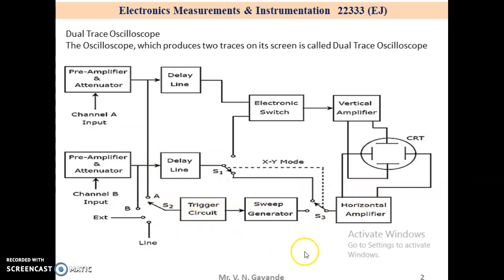The horizontal deflection system is common for both input signals or channels. The horizontal deflection system consists of a trigger circuit, sweep generator, horizontal amplifier, and horizontal deflection plates. I hope you understood. Thank you.